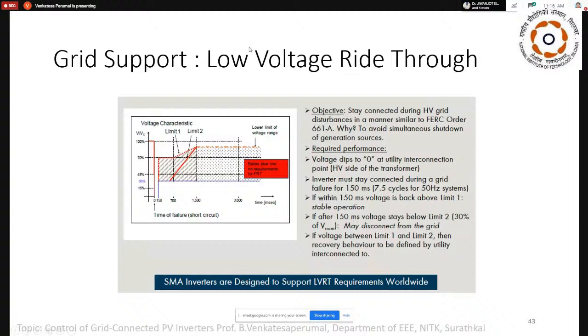So low voltage ride through, this is the condition we need to implement for the grid control of a grid connected inverter. The condition talks about 150 milliseconds: even if the system has a dead short, you need not remove the inverter from the grid. It has to still be connected to the grid. That 150 milliseconds is nothing but 7.5 cycles for 50 hertz. Even if the voltage at the terminal suddenly goes to 0 volt because of a dead short, it should not disconnect up to 150 milliseconds.